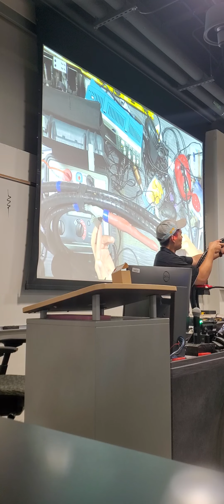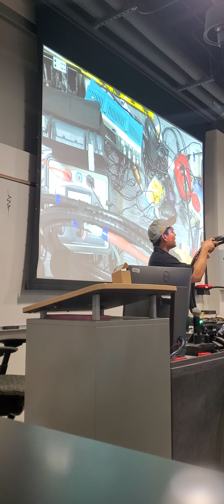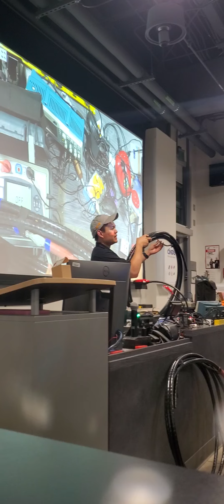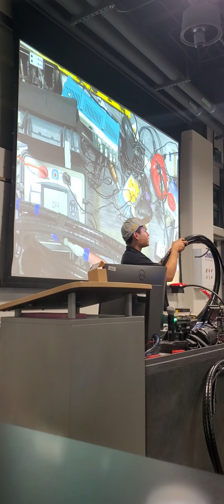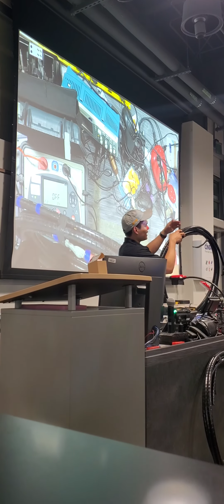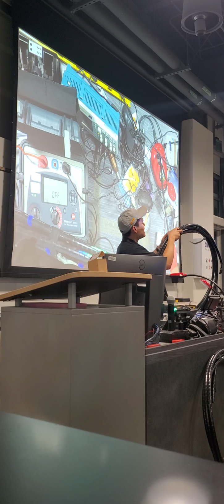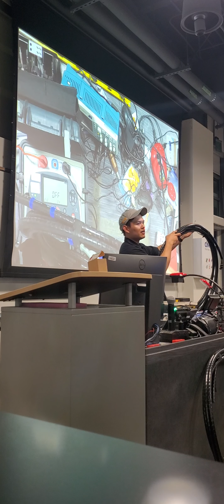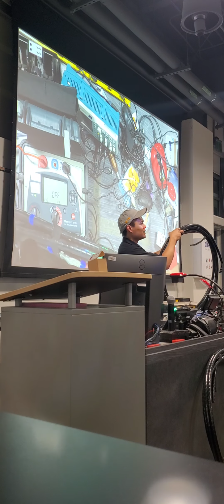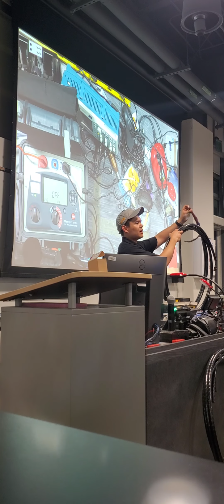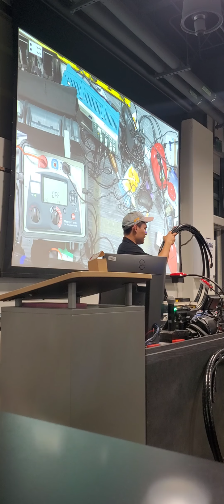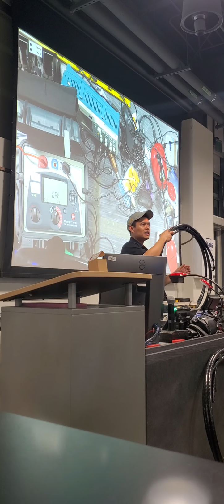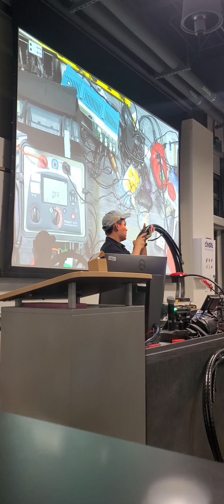Remember this guy from last week? Yeah. All right. Yeah, and what is that? What will this tell us if we test between here and here? Again, that's when we have that cutaway, that cross-sectional area that says we're testing the bulk of the insulation across the whole insulation. So anything that leaks to the outside will be picked up by this guy, right? So this is a suitable phase to ground test. So current carrying conductor, right? Accessible termination, as well as the tape shield that goes all the way around the whole cable, hundreds and hundreds of feet. Right? So by testing phase to ground, we all understand that this is a very useful test.